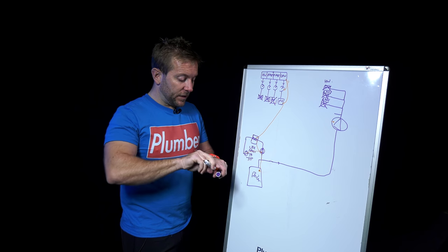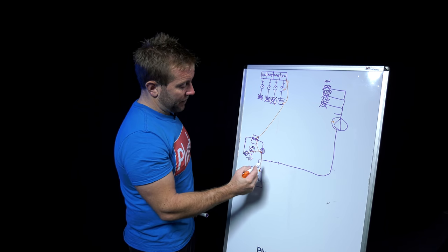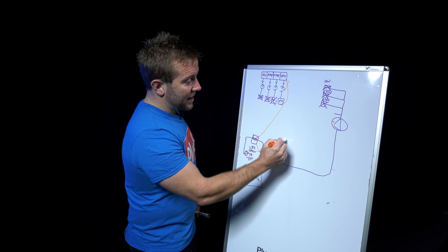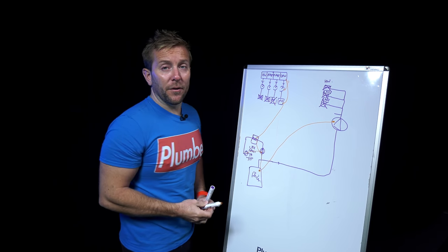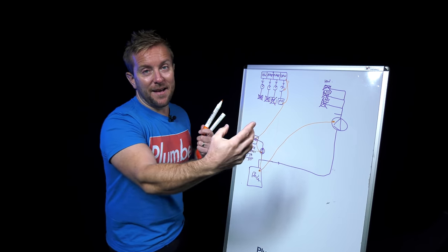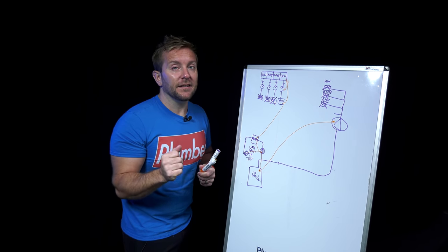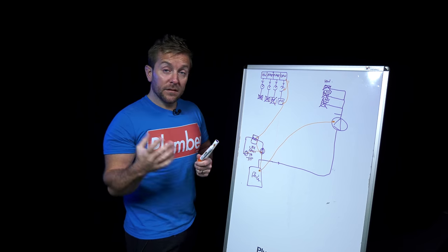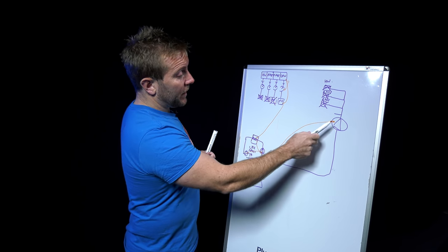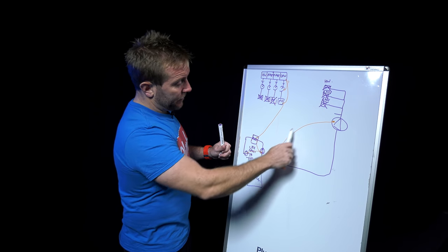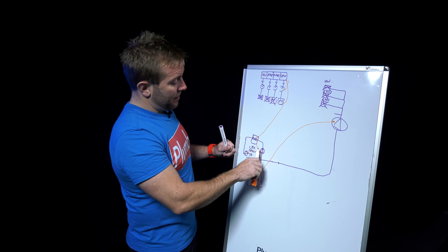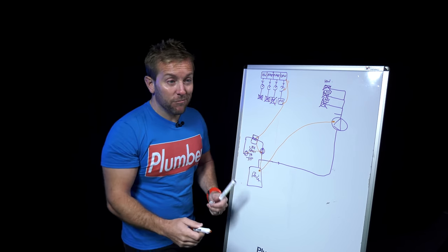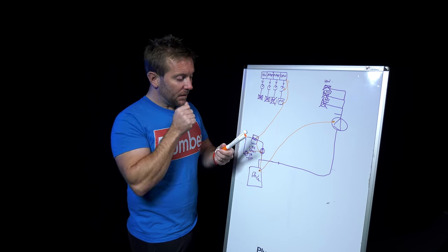So what's going to happen? Because we know that the boiler live and that pump up in the airing cupboard live is shared, it's going to send a live to that pump. That pump's going to cut in, but none of these valves are open. You're going to get just like a pressure behind there, you don't want that. So what we do, we use relays to interrupt that signal back and forth. The same works the other way around. Say one of these came on, it called that live, but the underfloor heating wasn't calling. The live gets sent to the boiler and the pump, but it also gets back to that pump. Everything starts coming on, don't want this at all. So this is when we use relays.